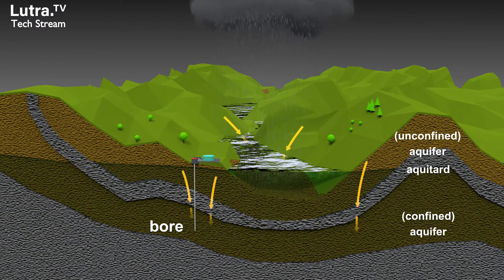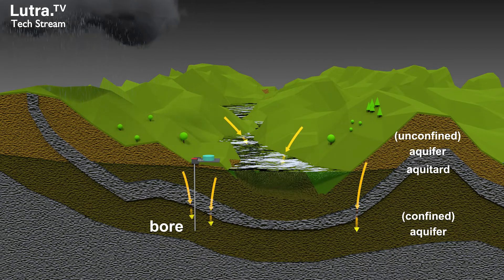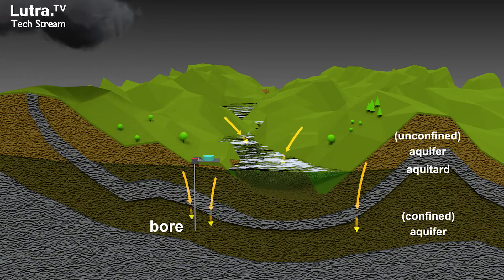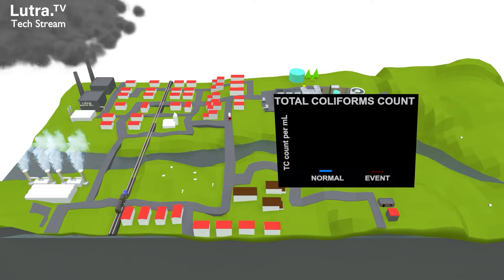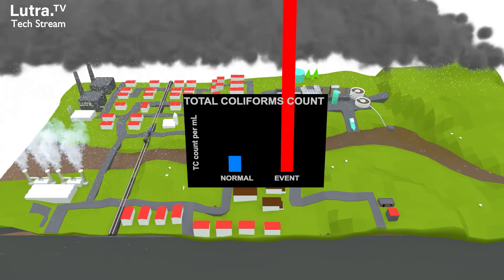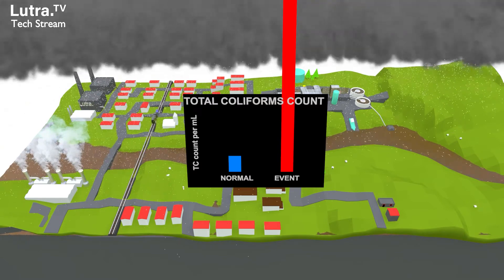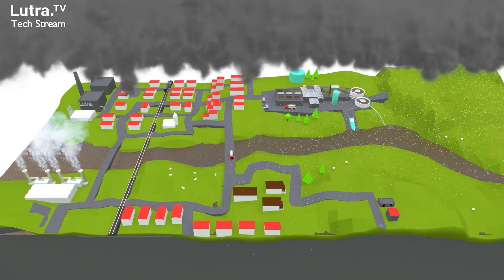You can see if water quality gets worse. For example, in a contamination event or runoff from strong weather events, you could have a baseline of 500 CFU of total coliforms, which is quite likely in river water. That might be the general baseline, but we need to understand the dynamics of our source water. A strong rain event can shoot that up to 10,000 or 20,000. We know these peaks associate with certain events, so in retrospect we can draw conclusions and expect these events.